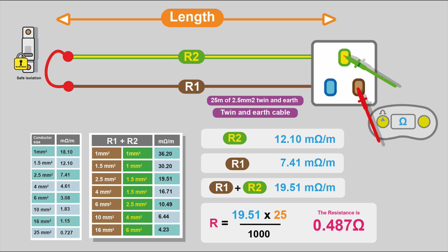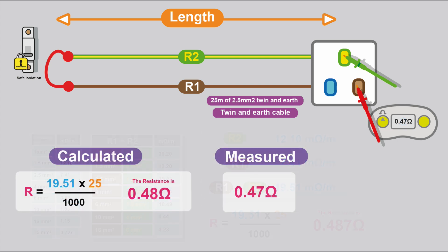And at the socket, you'll take your reading between the line and the CPC, and you'll record that reading as your R1 plus R2 for that circuit. And if we actually calculate that value, 2.5 line conductor and 1.5 millimetre squared CPC gives us a milliohms per metre of 19.51. It's the same maths as before. The resistance of that circuit is 19.51 times 25, it's 25 metres in length, divide by 1000, and it gives us a resistance of 0.487 ohms.